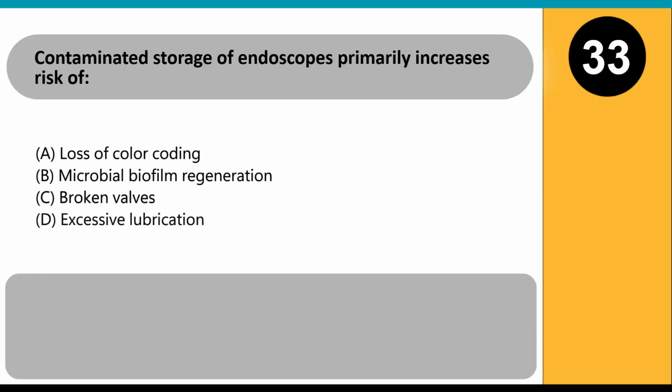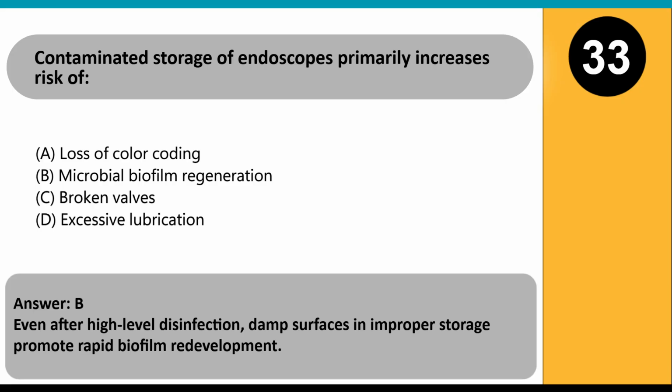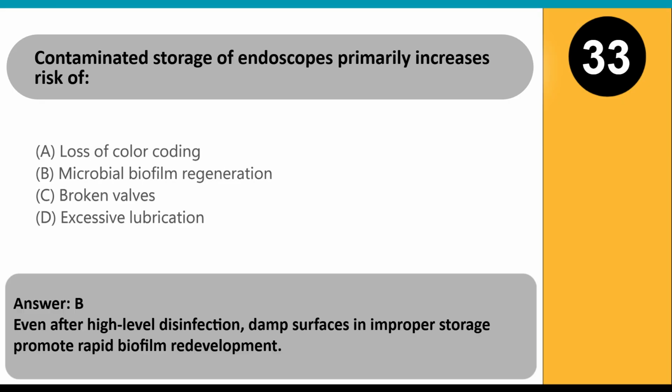Contaminated storage of endoscopes primarily increases risk of: A. Loss of color coding. B. Microbial biofilm regeneration. C. Broken valves. D. Excessive lubrication. Answer, B. Even after high-level disinfection, damp surfaces and improper storage promote rapid biofilm redevelopment.